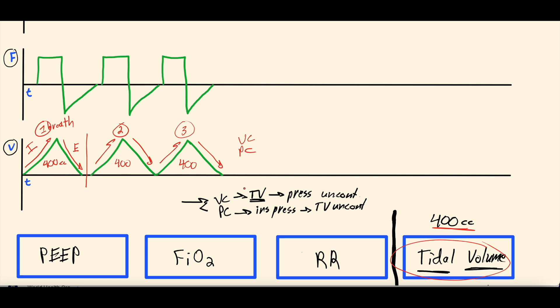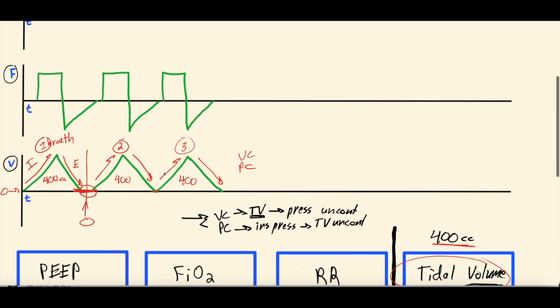The volume scalar looks similar between volume control and pressure control — the shape, inspiration up and expiration down, is about the same. The volume goes up when they inspire, down when they expire, hopefully returning to zero because you breathe out all the air you breathed in. Between breaths, volume sits at zero. This repeats for each breath cycle.